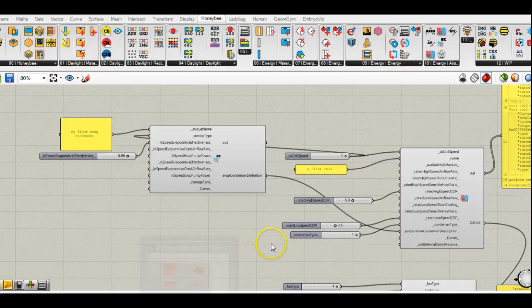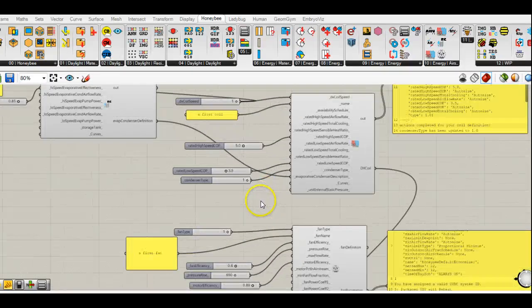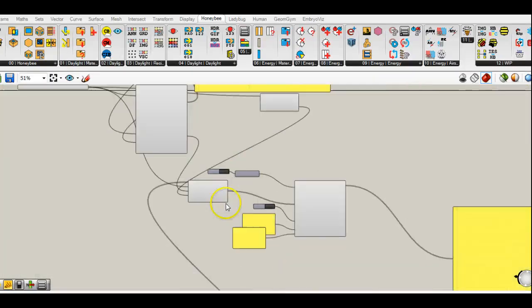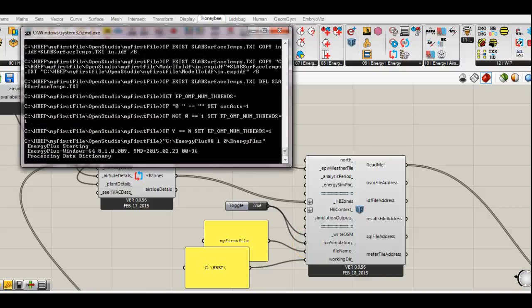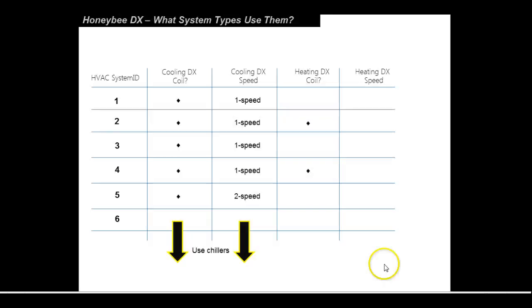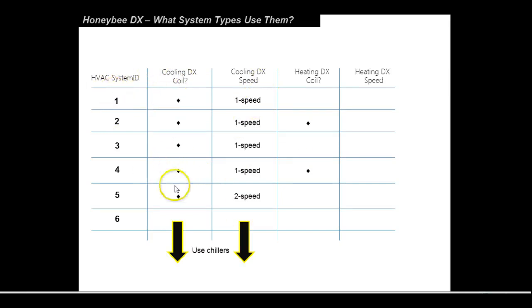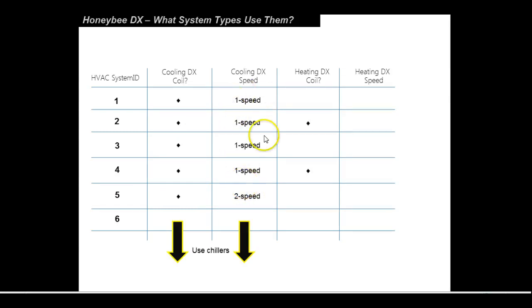So that's pretty much the overview. And once you're ready to run, you can just hit run simulation. And sometimes people ask me a couple other things and I'll just go over this really quickly. So we're just talking about cooling coils here. So here's a little list for you. Systems one through five, all use DX coils. Anything six or above uses chillers. So you don't need to worry about that. And here's a little guide for you. So anything one through four is going to be using a one speed. Anything five or above or five will use a two speed. Any of these can have evaporative condensers, but I think in practice, it's pretty rare for especially system types one and two to use evaporative condensers.